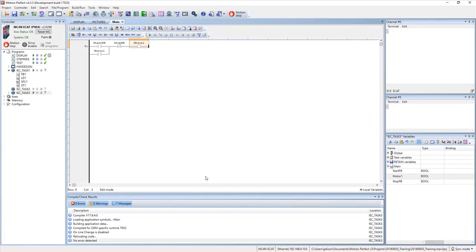So if someone presses start but not stop, it will energize motor 1 as long as the stop push button is not pressed. Motor 1 will always energize, sort of re-energize itself, so motor 1 will have power continuously. The reason the stop push button is normally closed is that physically the stop push button is a normally closed button. I think it's actually part of the safety requirements. It has to be normally closed, because if there's no power, then it has to stop in that situation.